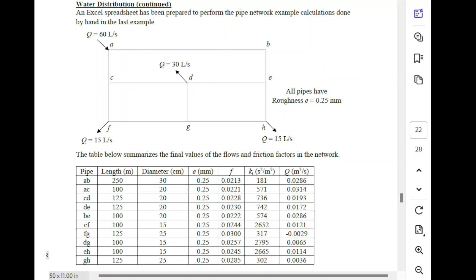This is a network that has 10 pipes. There are eight nodes labeled A, B, C, D, E, F, G, H, and the pipes would be AB, AC, BE, CD, DE, and so on. If you count them up, it should be 10 pipes and eight nodes, so this is a lot more complicated. Water comes in through a tower at point A at a fixed value of 60 liters per second, and it's being pulled out at D, F, and H — D at 30 liters per second, and F and H at 15. So 60 in and 60 out, but at three different points.